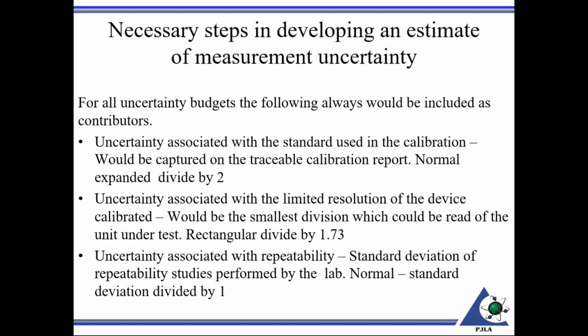That is usually the uncertainty divided by 2. Second, with all calibrations, you typically have an uncertainty associated with the limited resolution of the device calibrated. This would be the actual smallest division which could be read on the unit under test, and that is a rectangular distribution. We'll depict these in a little bit, as far as what a rectangular distribution is and what it looks like. It has a divisor of typically 1.73. Third, repeatability. That's typically a normal distribution, and it's the standard deviation of repeatability studies performed by the lab.